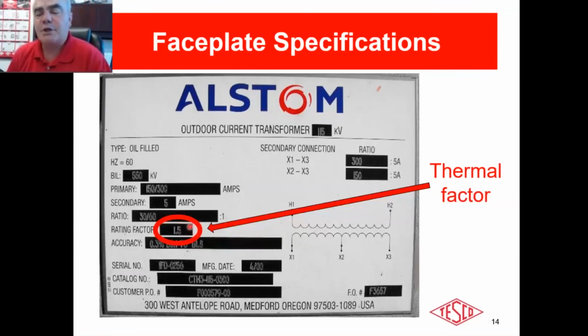We're going to talk about the accuracy in just a second, but what most people don't realize is if this is a 400 to 5 transformer, you would expect that its accuracy is going to be best up to that rating, 400 amps. In fact, that's not the case. It's actually best from 400 amps up to the limit of its thermal rating factor. So in this particular case, this 300 to 5 transformer, it will measure the best. It will measure at its rated accuracy, at its faceplate accuracy, between 300 and 450 amps. If I put less than 300 amps on the primary, I will get less than the rated accuracy on this transformer. And we'll talk about that more in a couple of slides. All right, but it's a very important thing to remember, and many people are not aware of that, okay?